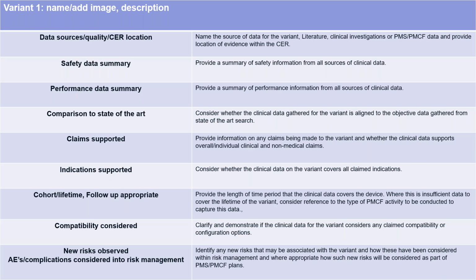We know that perhaps certain variants may have certain claims, particularly if they're variants that are supporting a specific patient population or a specific stage of disease. Also making sure that for devices where there are multiple indications, really to look at whether the data that you hold is covering each of those indications that may be assigned. And also looking at the lifetime of the data that's held for that specific variant and what follow-up may be required in terms of the type of PMCF activity that you can gather that data.